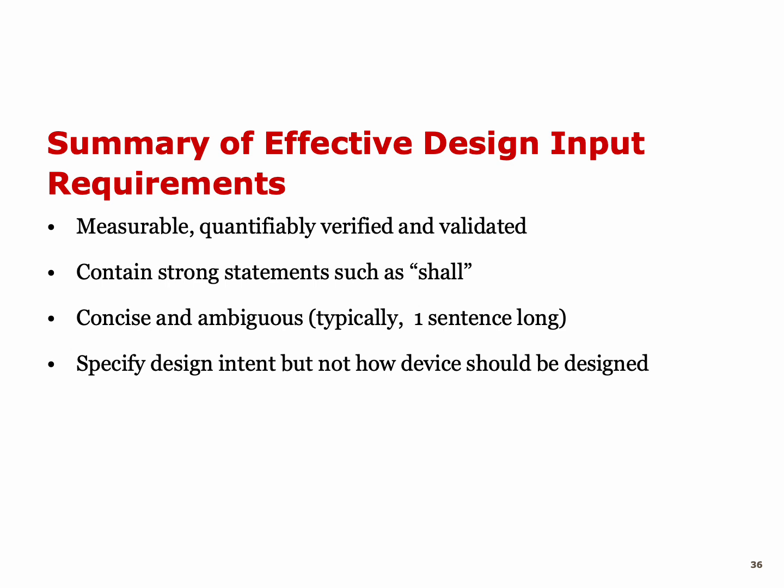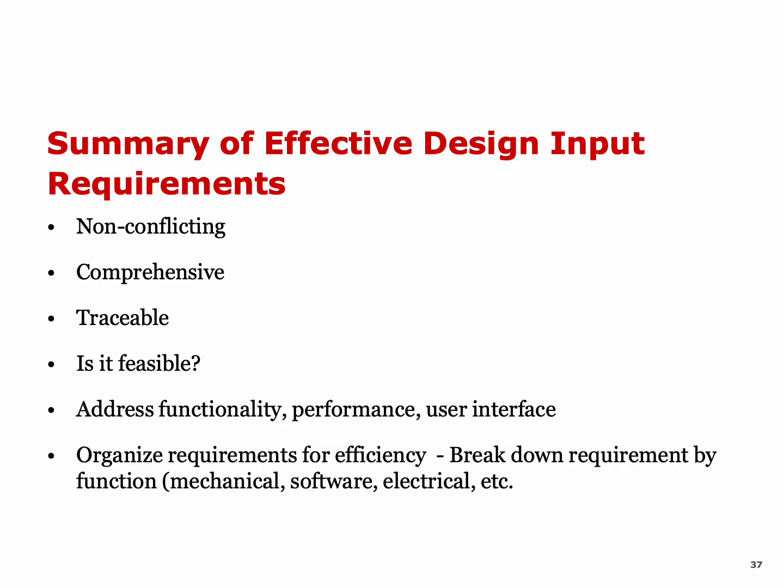We look into, again, what are the functions that we are looking at in a device. So this is for the design input, and the design input is just, again, as we already talked about, going to be measurable, quantifiable, verified, and validated function. And this is coming, again, from the interaction between the patients, physicians, and the engineer. Now, of course, the design input should not be conflicting, should be comprehensive, must be traceable, and we have to discuss if it's feasible with the existing technologies or tools that we have.